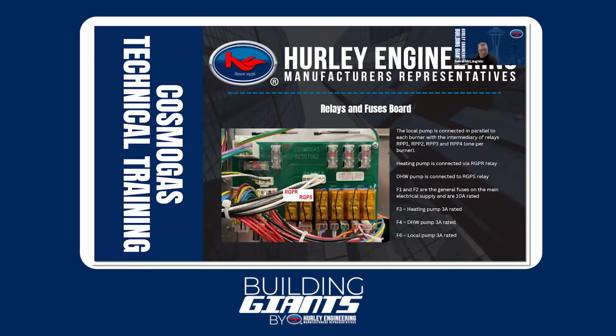So this is our standard relay board, and not too much here other than to note that we do have the fuses, all of our pump outputs if you need them for heating pumps, domestic water pumps, local pumps, if you're doing primary, secondary, that sort of thing. They're controlled through these relays. They're all rated at 3 amps. If you're going to pull more than 3 amps, then we'd have to have isolation relays. And I've even got a small schematic later on that'll show you how that isolation relay could be installed.